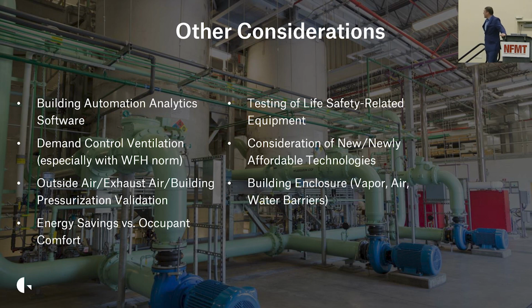Demand control ventilation - that's essentially looking at CO2 levels and figuring out, should I augment my ventilation, can I reduce it? Because especially in warmer, more humid climates, the more outside air you pull in, the more you're going to be paying to condition that outside air.